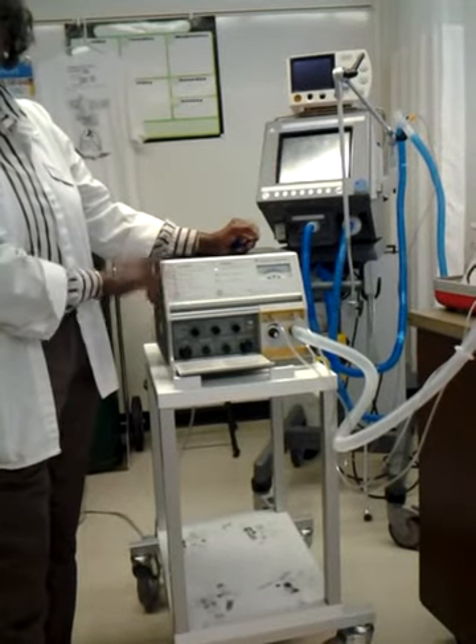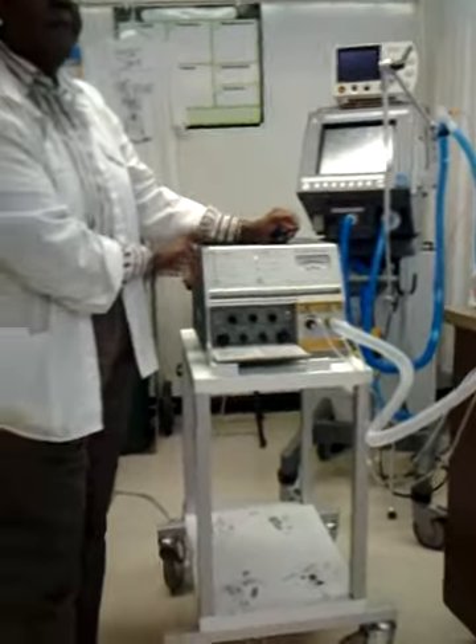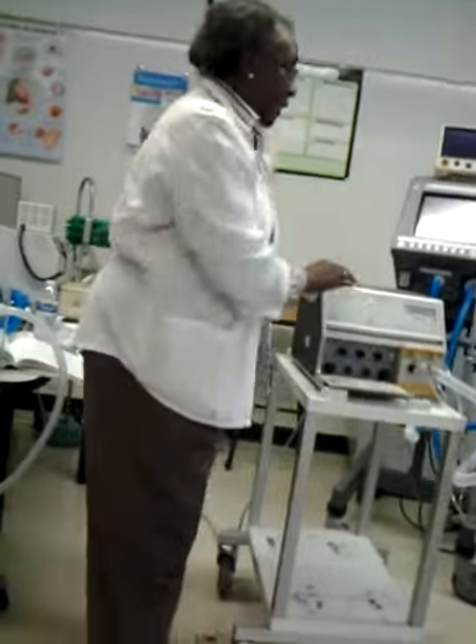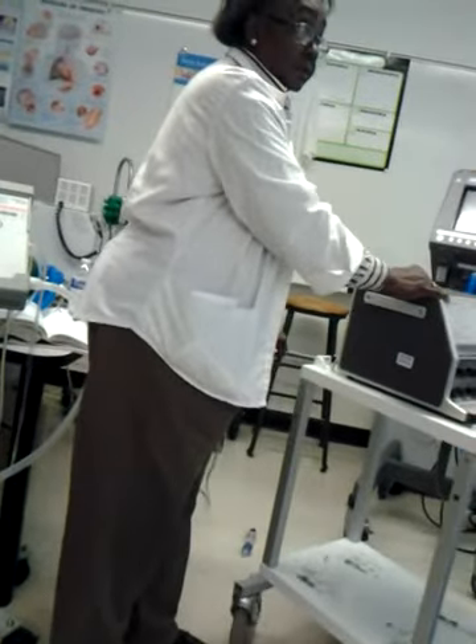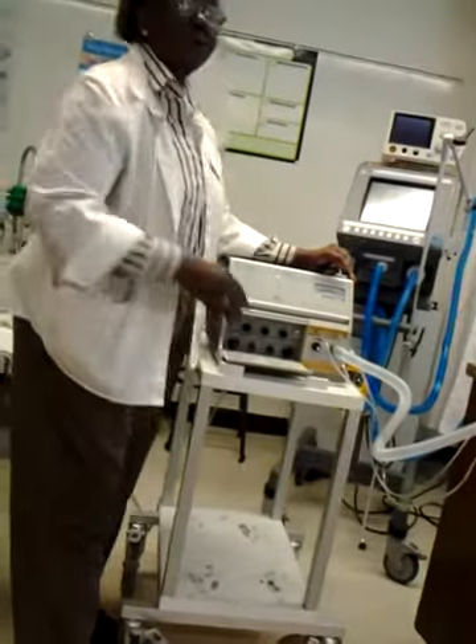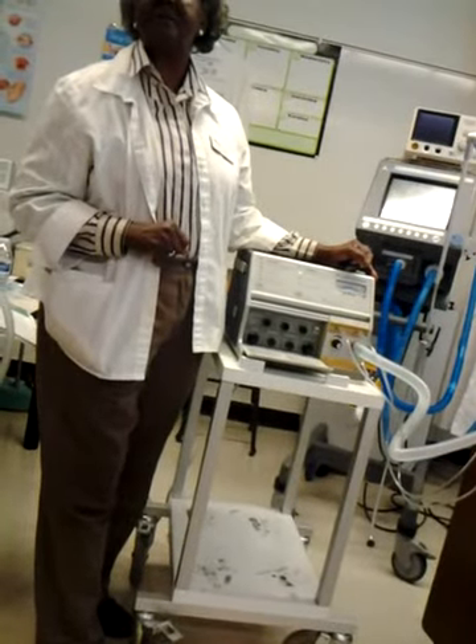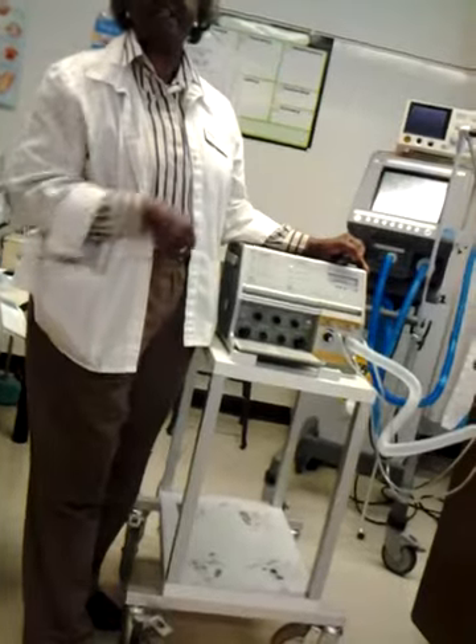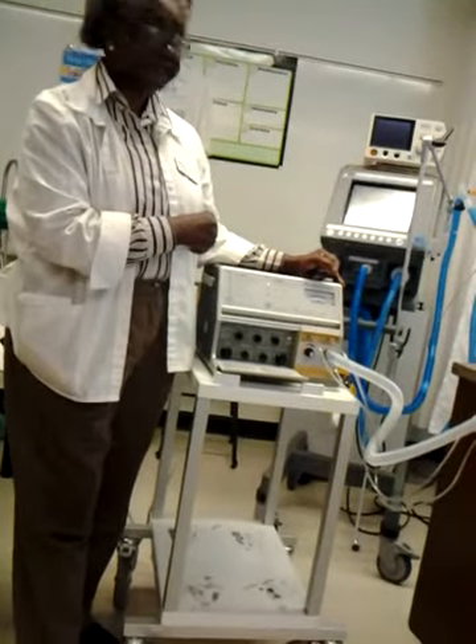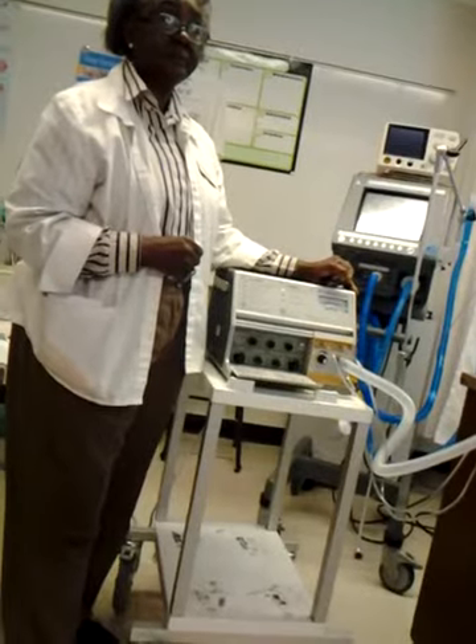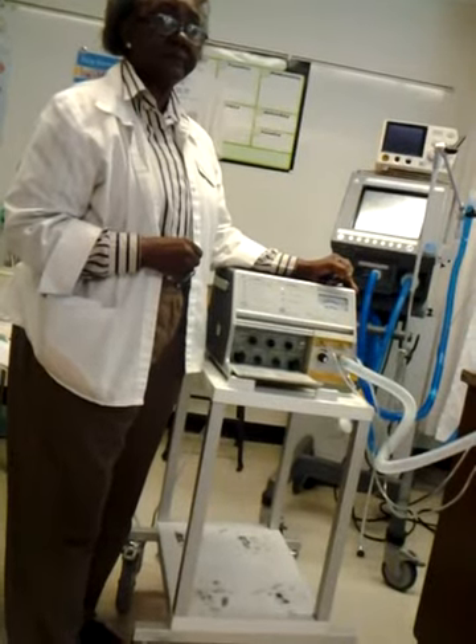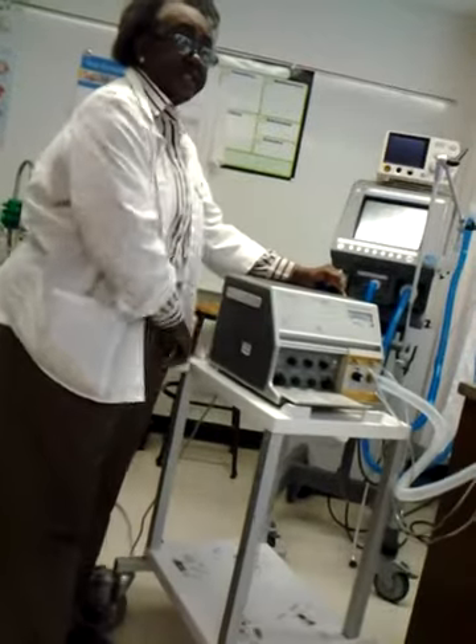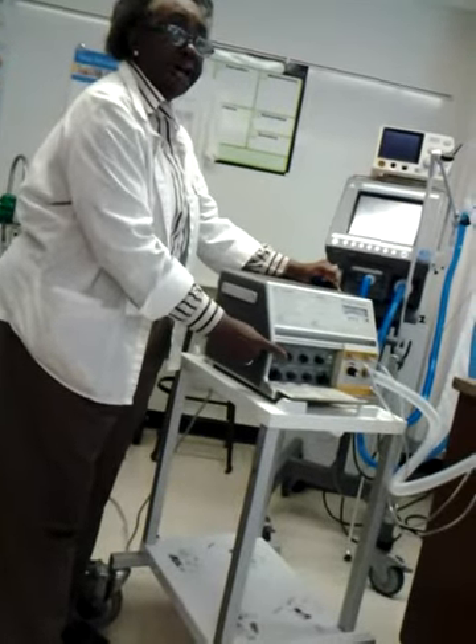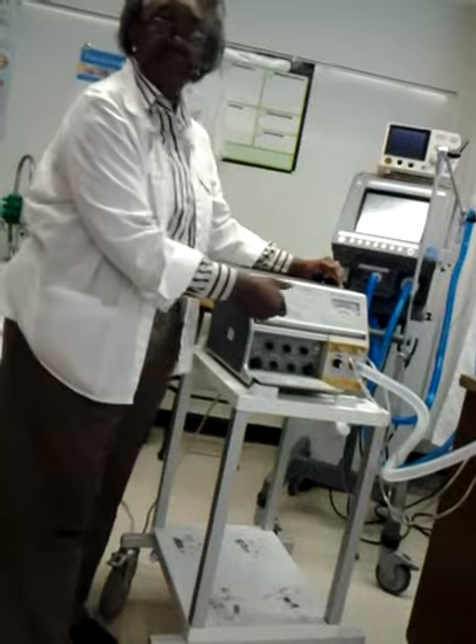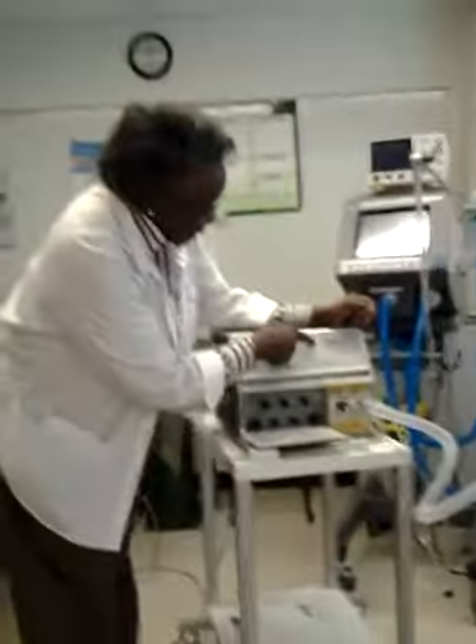It does have an internal backup battery, but it can also be hooked up to an external battery, like I say, a big car battery, if you don't have it plugged into the wall. It should be plugged into the wall at all times. So there's no SST that we have to do on this? No particular SST. It runs its own little test and you turn it on. It's on standby, and when you're ready, you put it in the mode you want. The on and off switch is in the back. You can turn it on, but keep it in standby. Then you can set all your parameters, and when you're ready to go, just put it in the mode that you want. And of course, you notice you have a pressure manometer here.